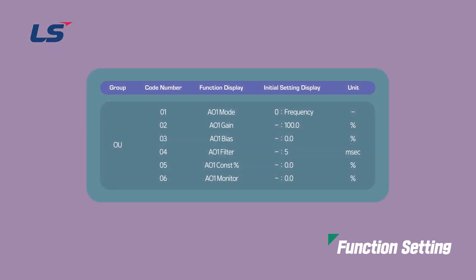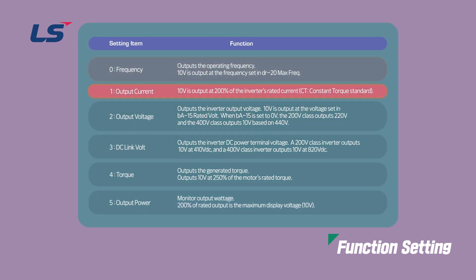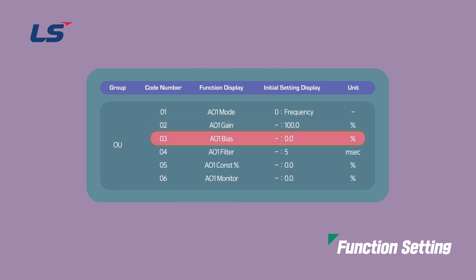Next, let's take an AC drive under 22 kW as an example. Parameters for analog output can be set in the OU group. The AO terminal is an analog output terminal; you can directly select the output items for AO in OU group number 1 parameter. Output items can be selected from operating frequency to fixed value output. In this video, we will select operating frequency 0. In OU group number 2, you can set the analog output gain, and in OU group number 3, you can set the bias value for analog output.